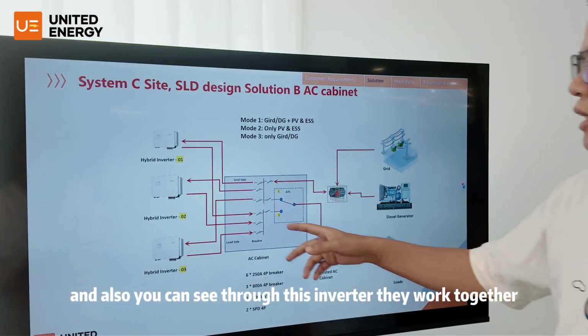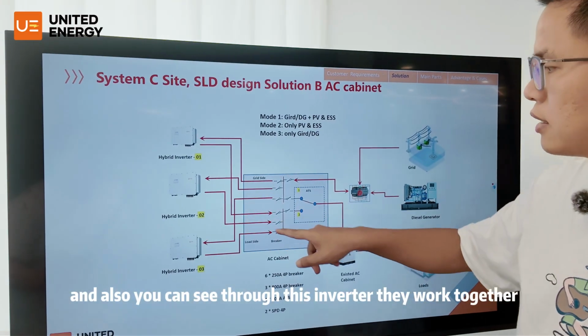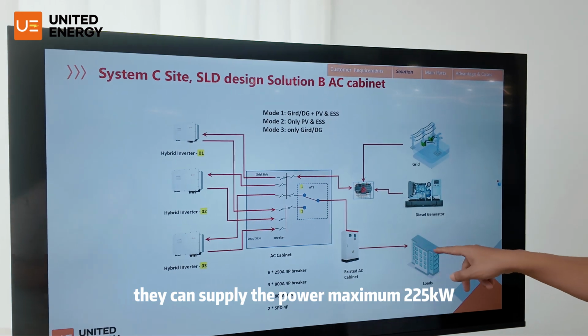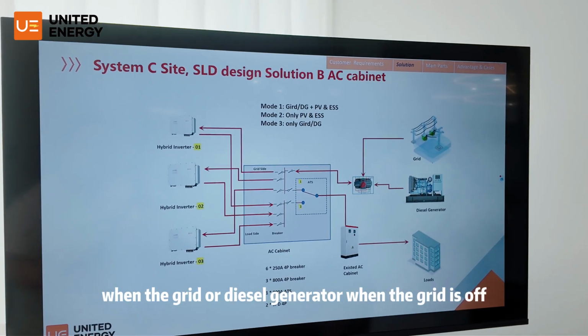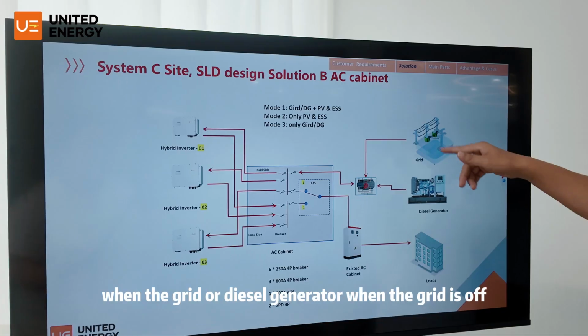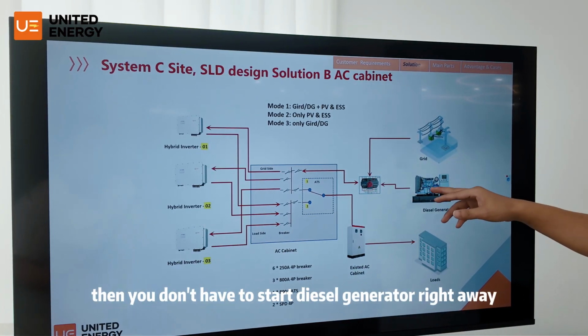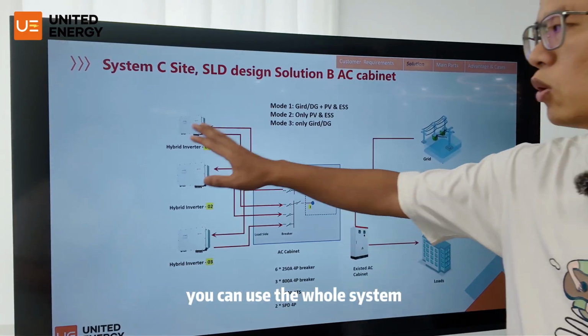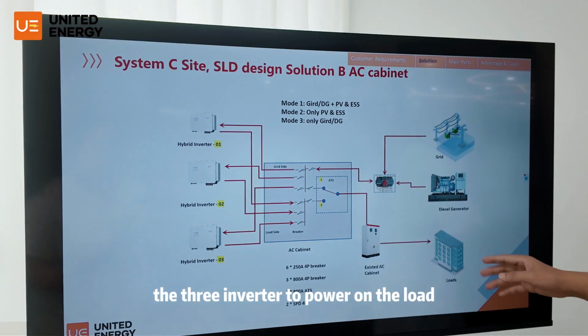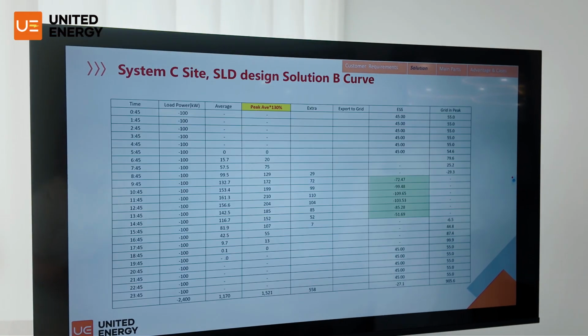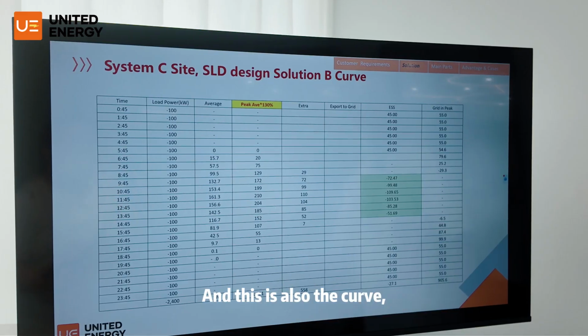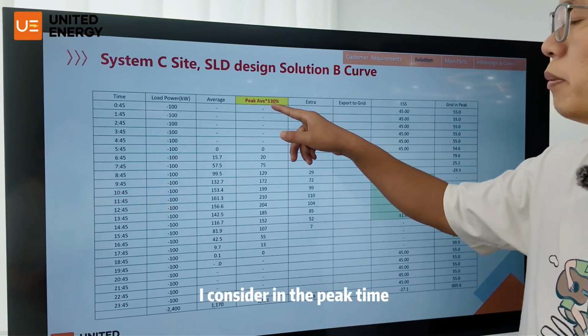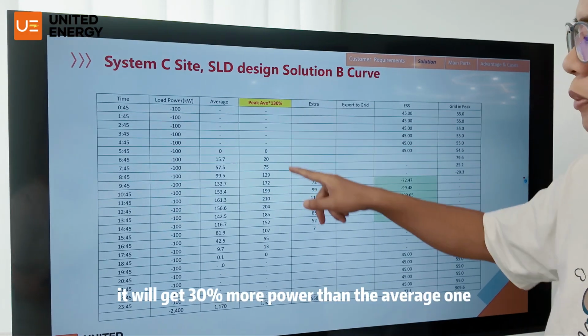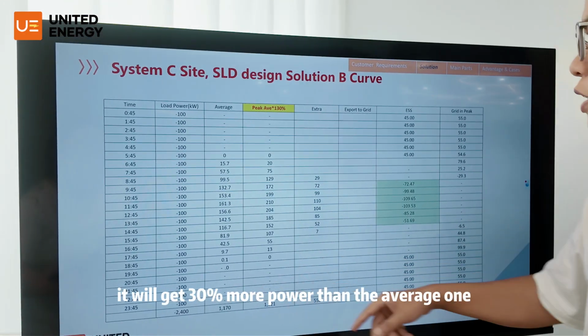And you can also see that the inverters work together and can supply a maximum power of 225 kilowatt. So when the grid is off, you don't have to start the diesel generator right away. You can use the whole system, the 3 inverters, to power the load. And this is also the curve. Also, I consider that in the peak time it will get 30% more power than the average.